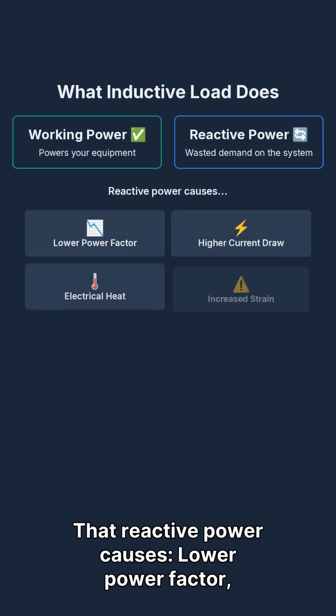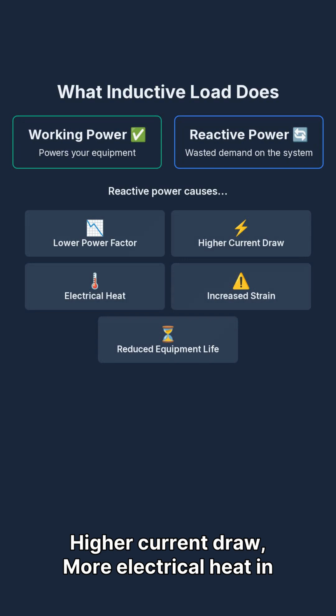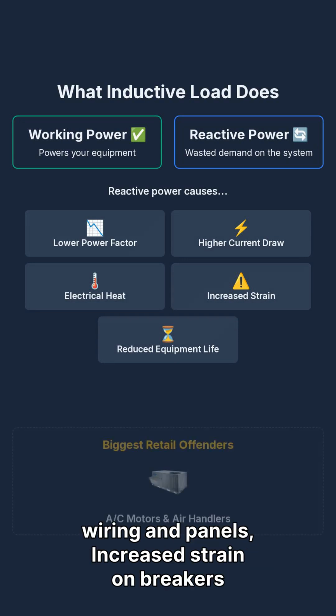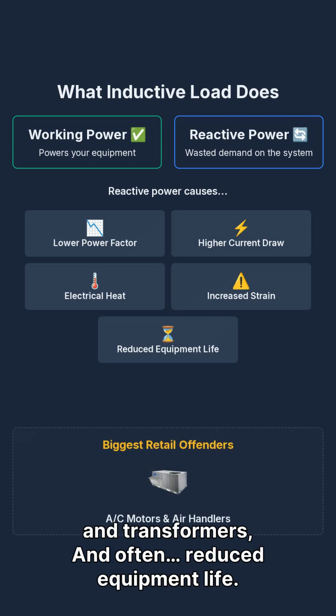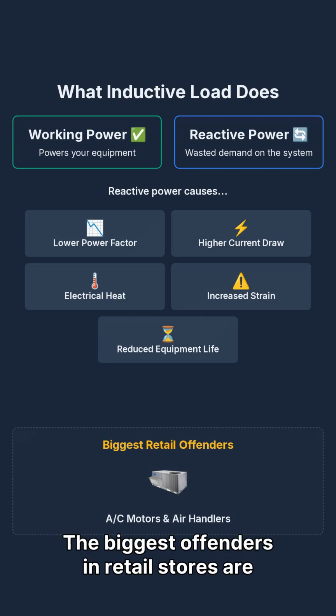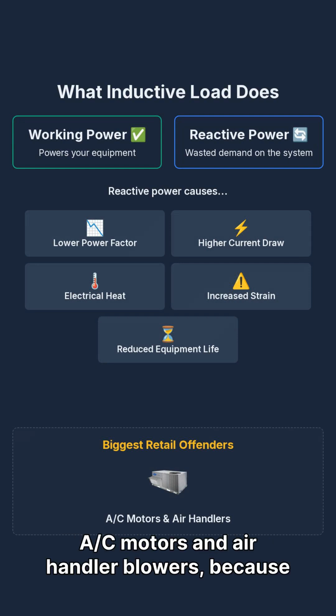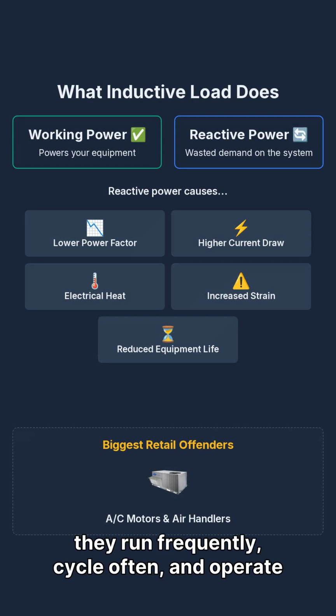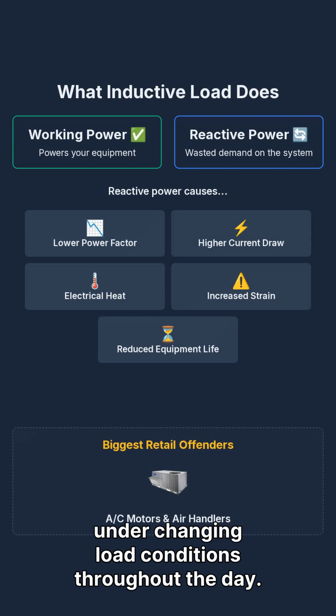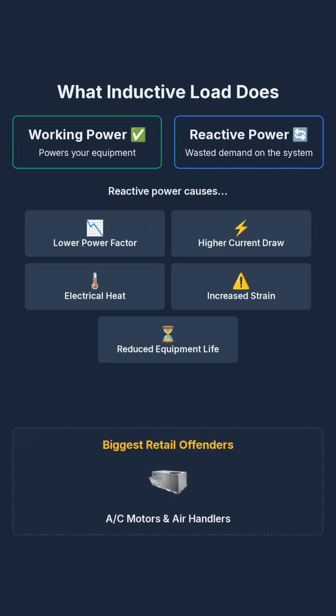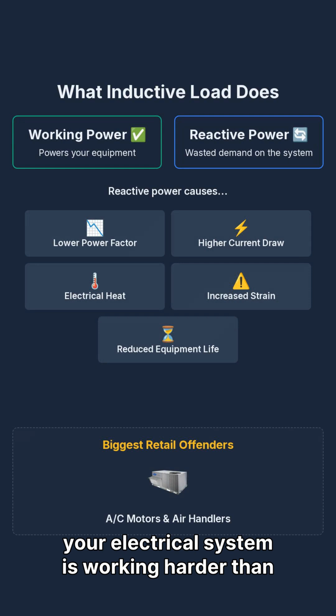That reactive power causes lower power factor, higher current draw, more electrical heat in wiring and panels, increased strain on breakers and transformers, and often reduced equipment life. The biggest offenders in retail stores are AC motors and air handler blowers because they run frequently, cycle often, and operate under changing load conditions throughout the day. So even if your store isn't busy, your electrical system is working harder than it needs to.